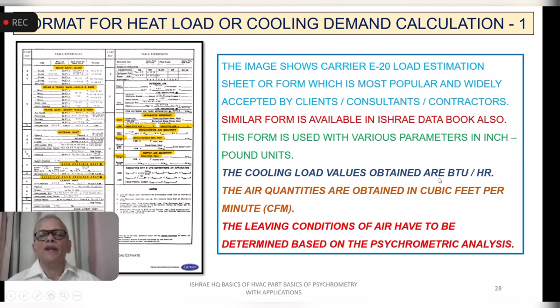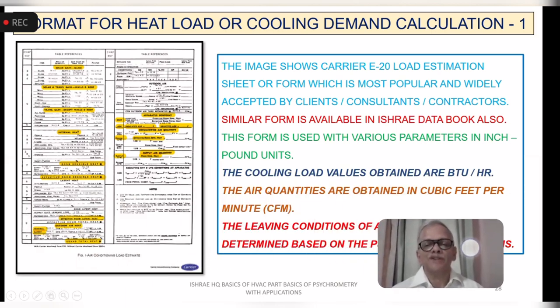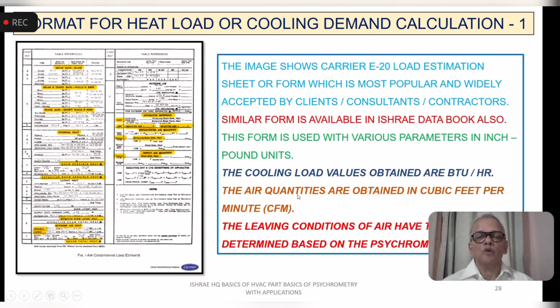The cooling load values are obtained in BTU per hour. This is British thermal unit per hour. What we calculate in the metric system will be in watts, which is joules per second. So joules will be equivalent to BTU, and per second, the time factor comes from hour to seconds. The air quantities are obtained in cubic feet per minute using this form and the calculations. And the leaving conditions of the air have to be determined based on the psychrometric analysis. So we'll have to go to the psychrometric chart and do that analysis for the process. How much air quantity is required is calculated. The purpose of this form is just to identify, okay, we have calculated the load, we have calculated the BTU per hour required of the system and the air quantity. Another factor is the sensible heat factor, which we'll see in the further slides.